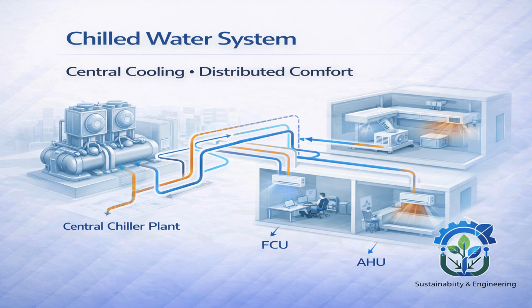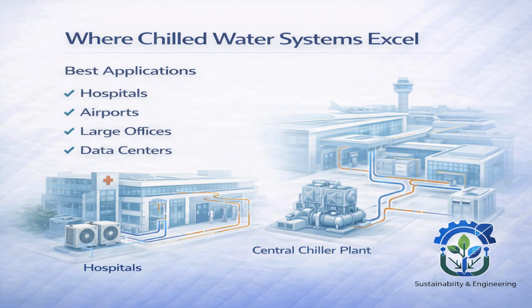Next, we are going to understand the roles of FCUs and AHUs. So now let's understand the terminals. FCUs are typically used for rooms, offices, and individual spaces. AHUs are used for large areas, fresh air treatment, and humidity control. This gives designers flexibility to control temperature, manage ventilation, and handle latent load effectively, something that becomes very important in hot and humid climates.